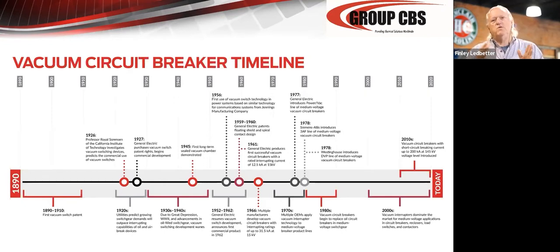So all the installed base since then has been vacuum breakers. Then a certain amount of people have gone back and updated or upgraded their vacuum gear, either by roll-in replacements, retrofits, replacing the old breaker, keeping the old switch gear, or simply taking the switch gear out completely and installing new vacuum gear. So through all of that, I would estimate that about 50% of the medium voltage equipment in the United States today is vacuum, and about 50% of it is air.